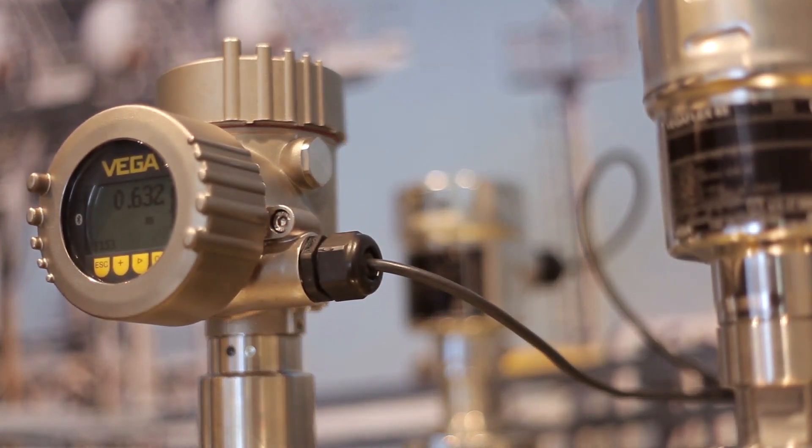How was the function test carried out until now? First, the level switch had to be removed even under difficult process conditions. Afterwards, it has to be checked manually with the medium, and finally the control system had to be checked if the signals were received correctly.